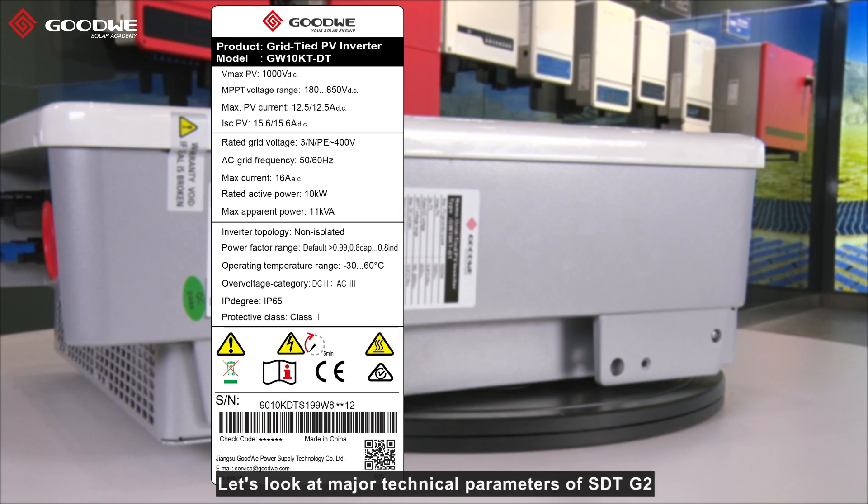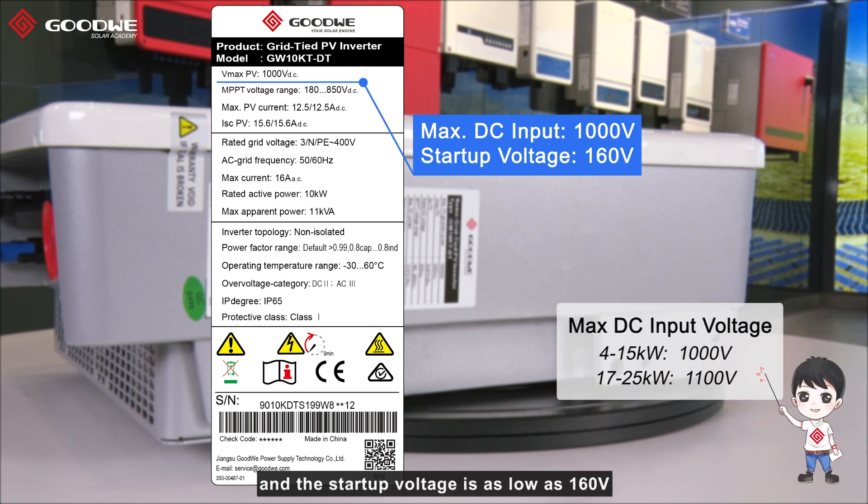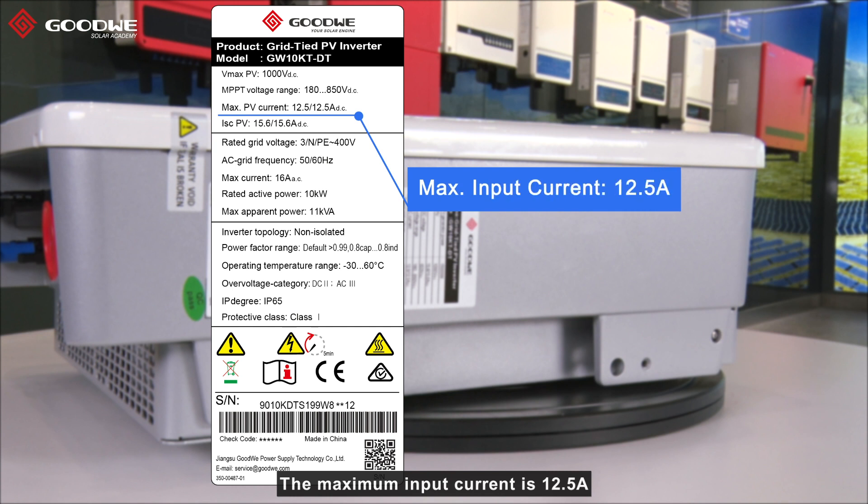Let's look at the major technical parameters of SDT G2. The maximum DC input voltage is 1000V and the start-up voltage is as low as 160V, which means SDT G2 can start to operate earlier in the morning and stop later in the evening, bringing extra generation. The maximum input current is 12.5A, making SDT G2 perfectly suitable for connection with high-powered and bifacial PV modules.